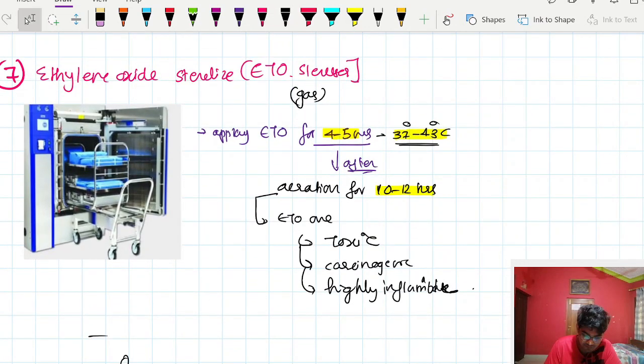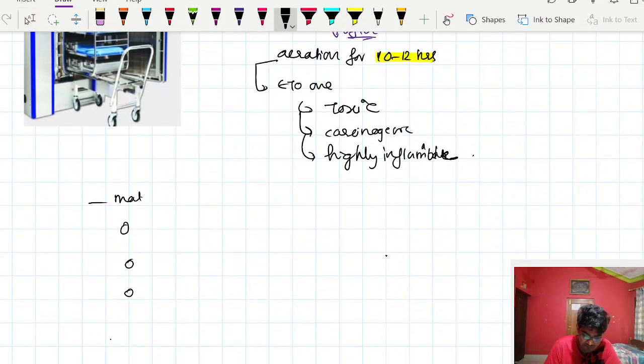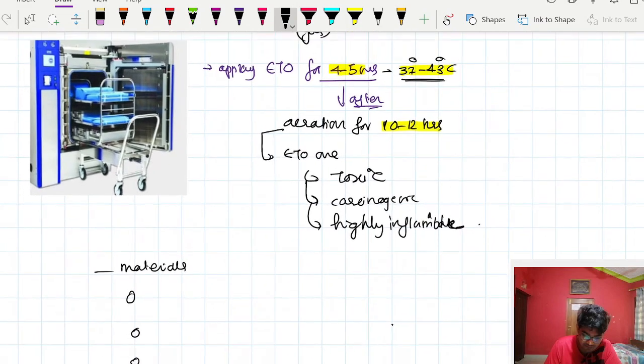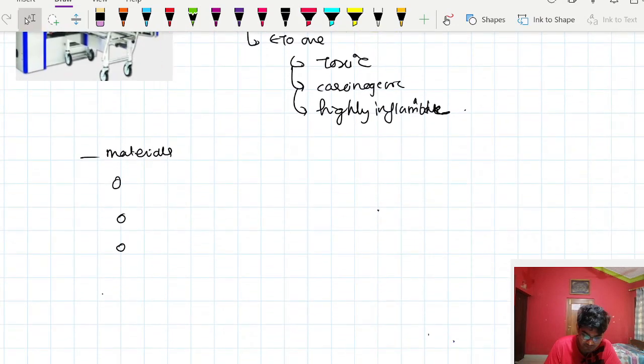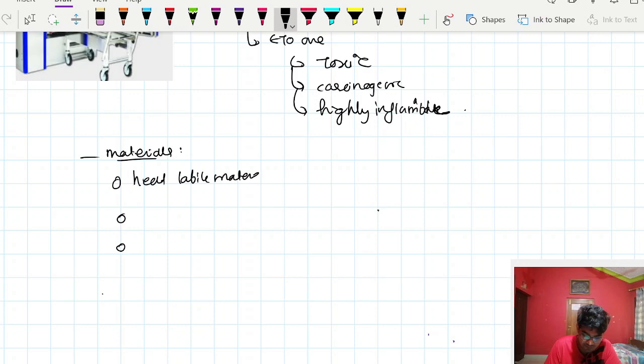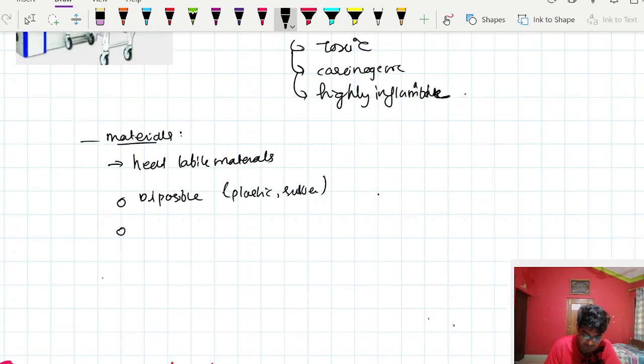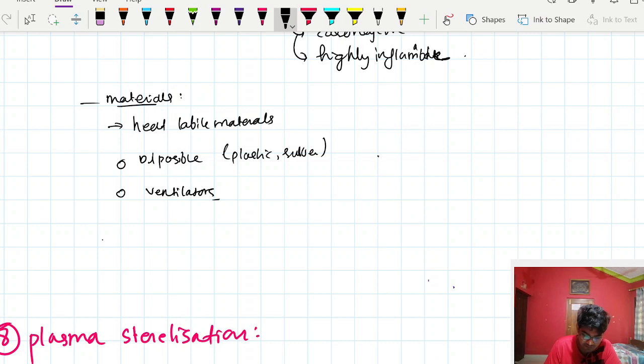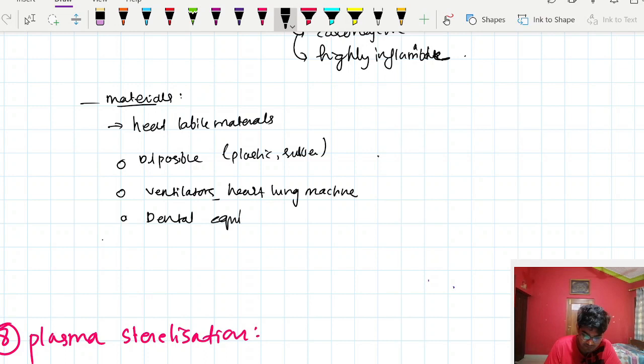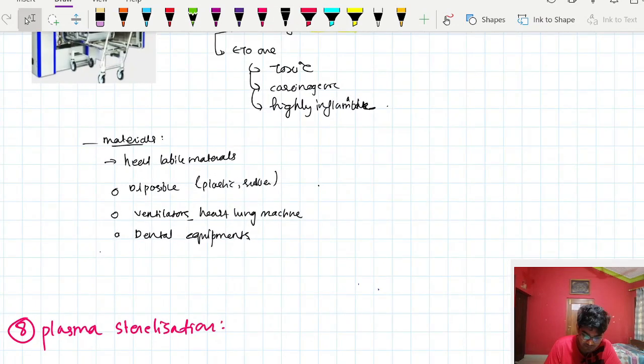The control for ETO sterilizer is Bacillus subtilis or Bacillus atrophaeus. The mechanism of ETO is that it is an alkylating agent — it destroys nucleic acids and proteins. Materials used include heat-labile materials like disposable plastics and rubber, ventilators, heart-lung machines, and dental equipment.